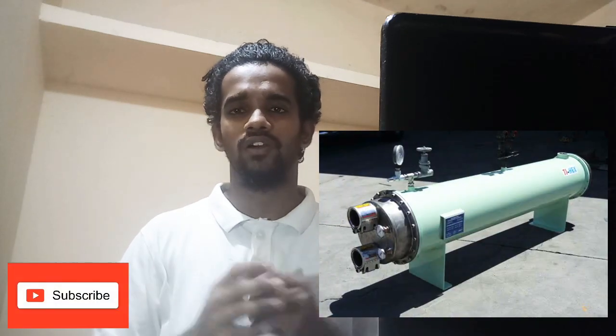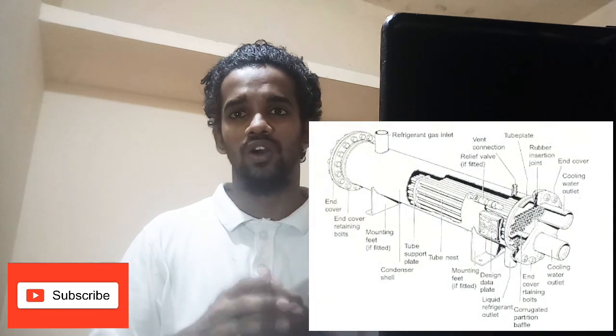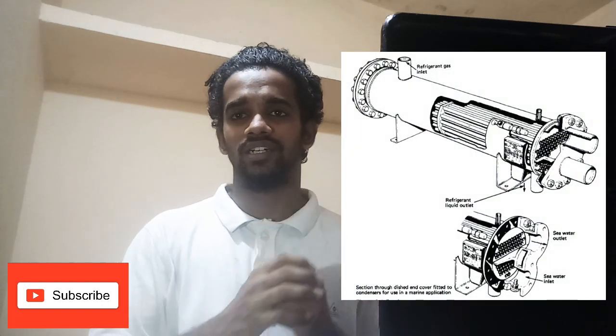As the pressure is being increased, the saturation temperature is being enhanced. Now talking about the condenser: here in the condenser, the refrigerant is being liquefied or subcooled to a temperature below the saturation temperature. The water or air in the condenser takes out the heat from the refrigerant — basically, the refrigerant is rejecting heat. The latent heat absorbed by the refrigerant in the evaporator is now being transferred to the water or air in the condenser. Note that the refrigerant maintains the same high pressure created by the compressor. The refrigerant then goes to the thermal expansion valve or metering device.